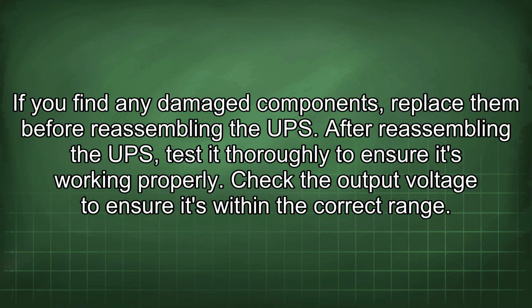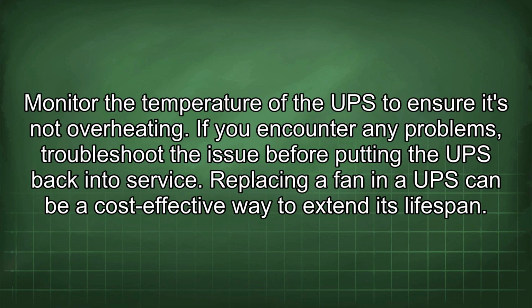After reassembling the UPS, test it thoroughly to ensure it's working properly. Check the output voltage to ensure it's within the correct range. Monitor the temperature of the UPS to ensure it's not overheating. If you encounter any problems, troubleshoot the issue before putting the UPS back into service. Replacing a fan in a UPS can be a cost-effective way to extend its lifespan.